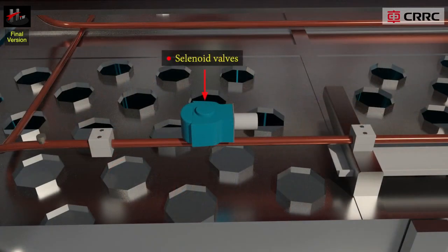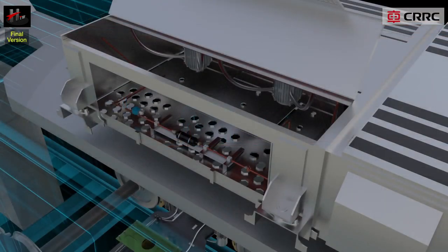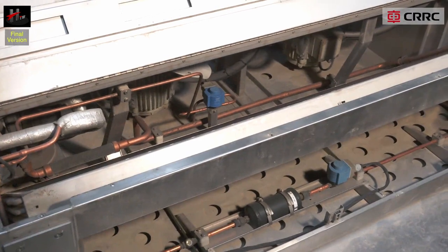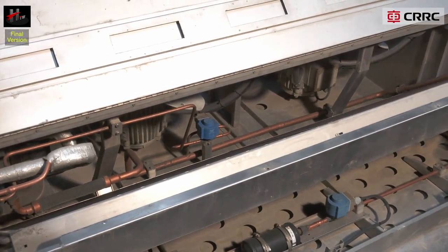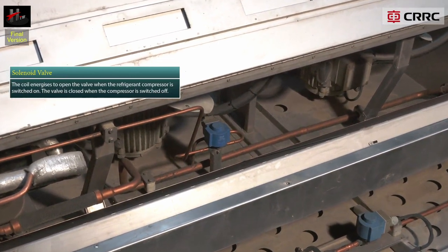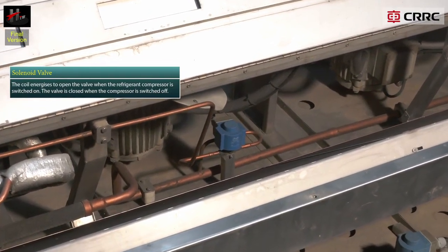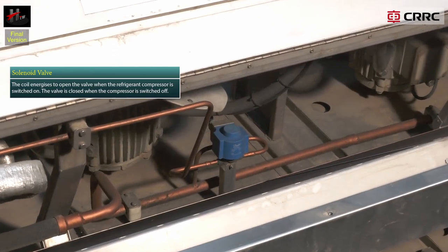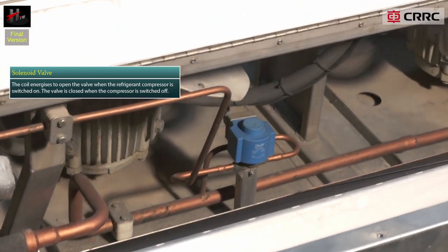The solenoid valve consists of two parts: the valve body installed in the refrigerant liquid line, and the solenoid coil connected to the electrical control system. The coil energizes to open the valve when the refrigerant compressor is switched on, and the valve is closed when the compressor is switched off.